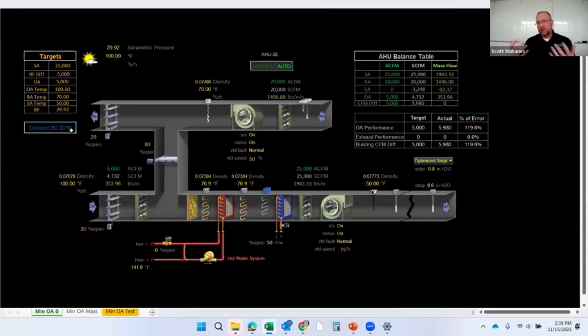There's a lot of things that you could talk about with this. There's some caveats to how air handler systems might change. You could have a closed relief damper and not have it open. The results are going to change slightly, but ultimately we have an issue related to the way we control airflow because volume can't do it correctly. And when you look at it from a mass flow conversion, you have to control it by mass flow. There's two problems that occur when we aren't controlling this correctly. There's more than that. Actually, let me summarize that for you.